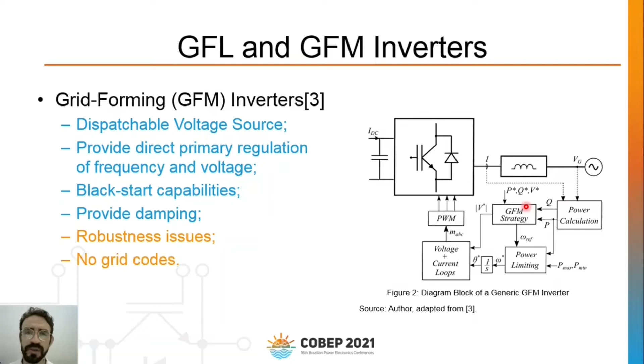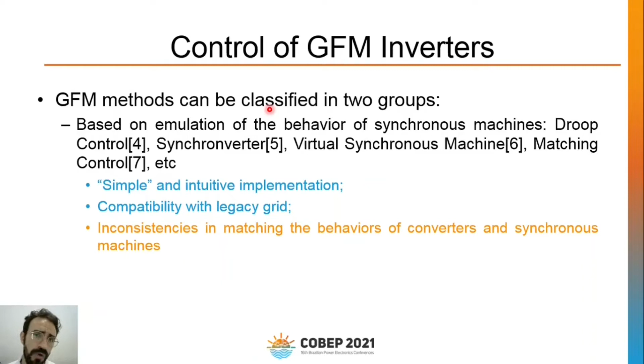Going into more details of the control of grid-forming inverters, these controls can be basically classified in two groups. The first one is the group of the controls based on the behavior of synchronous machines in different levels of abstraction. The main motivation for the development of these controls is their simple and intuitive implementation, since we have a lot of experience with the models and the control of synchronous machines. An important point is their compatibility with the legacy grid, since our current grids have their generation based on synchronous machines, so controlling an inverter to behave like a synchronous machine is a great opportunity for this compatibility. On the other hand, matching the behaviors of inverters and synchronous machines has some problems as they are different in their nature, which makes it not clear if this approach is the best option for the control of grid-forming inverters.